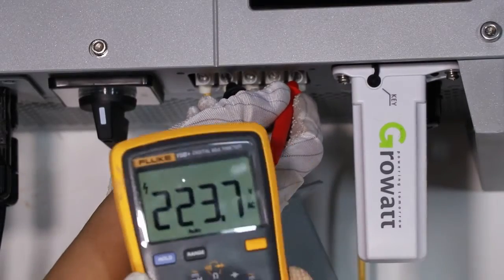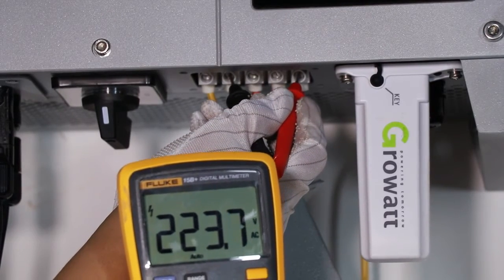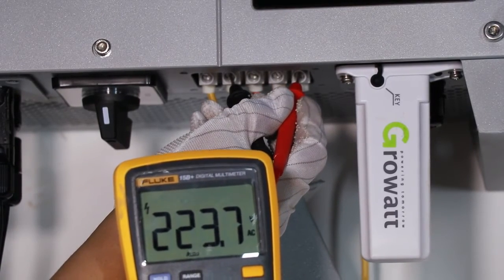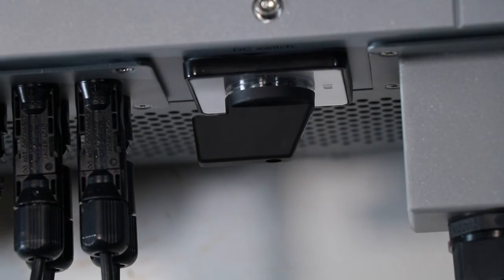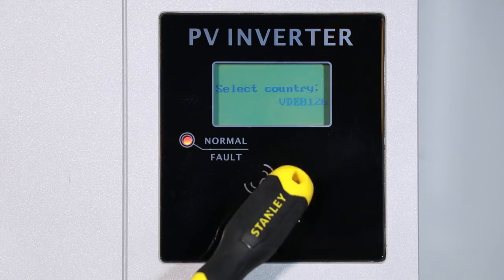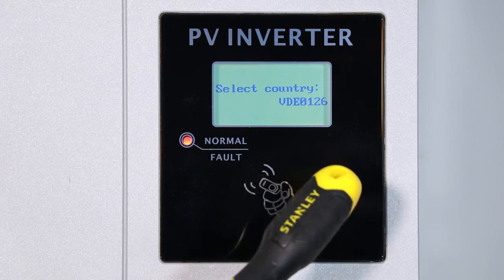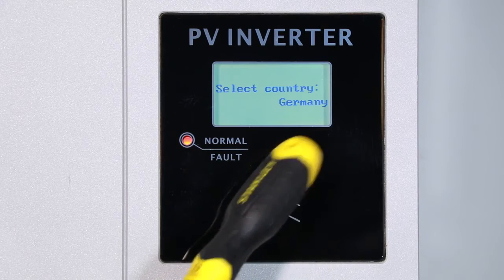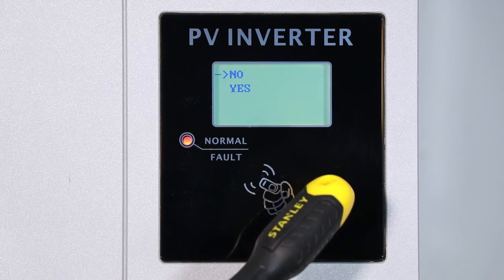Use a multimeter to check the PV input voltage and AC voltage on the inverter terminal. Make sure they are correct, then switch on the inverter DC switch to start up commissioning. The inverter LCD display will show a prompt to select the country. Tap the inverter's touch control panel to shift between countries, and double-tap quickly to confirm.